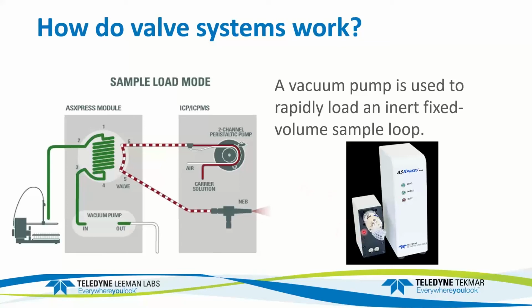To run a sample, the vacuum pump turns on, and that basically sucks the sample and fills up a sample loop, which is right here. And we'll show you one in detail in a second. Then that goes to the vacuum pump, then it goes out to waste, and that fills up this sample loop very quickly. In this particular example, since we only had two 2-second integrations, I used a 1 mL sample loop. There are larger sample loops for applications where the integration time can't be short, and you may have 3 30-second integration times, but you can still eliminate your uptake and rinse cycles and minimize the amount of time wasted for that.